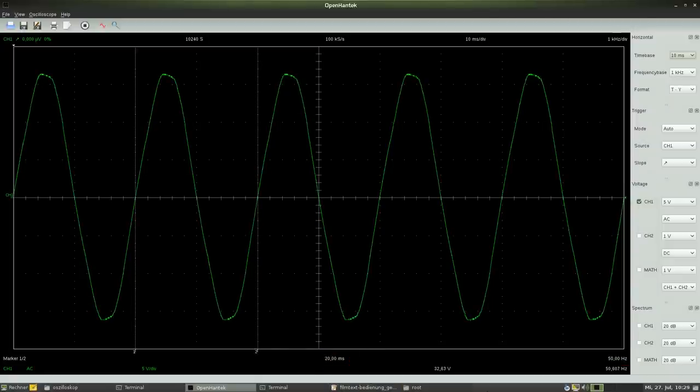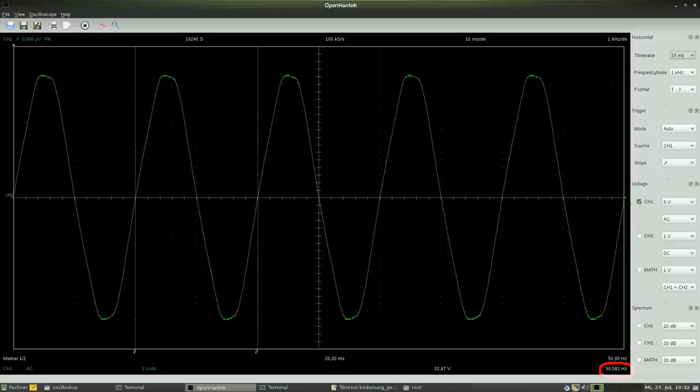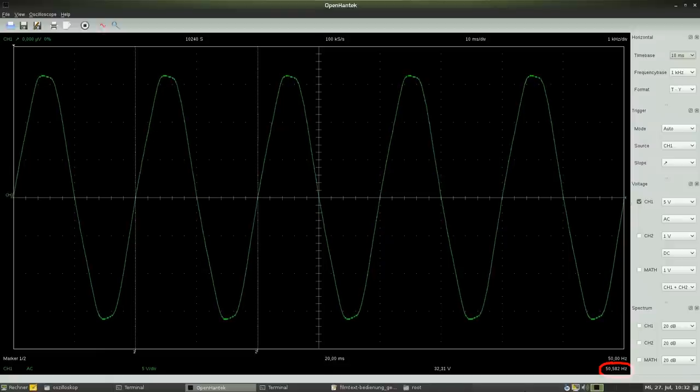Furthermore, the frequency of the attached AC voltage is automatically calculated by the software and we can read a slightly different value of 50.582 Hz.